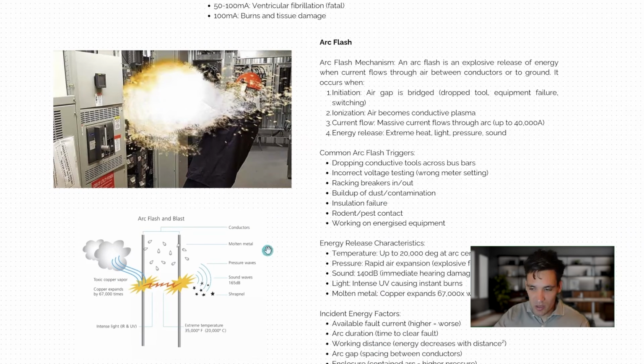So most modern switchboards will actually have specialist arc flash venting. So when there's a fault, it contains the arc and ventilates it out the back of the switchboard where it's likely that someone isn't going to come into contact with it.